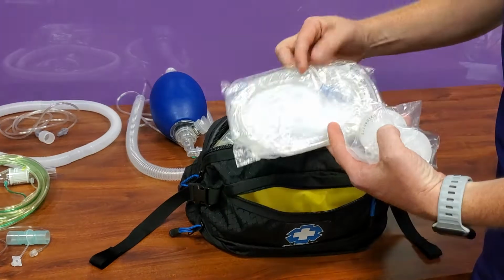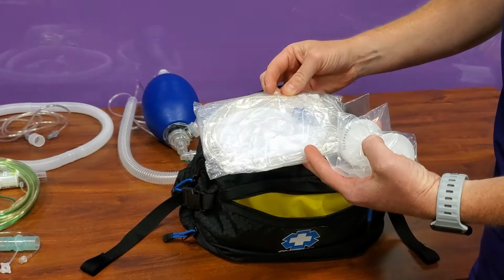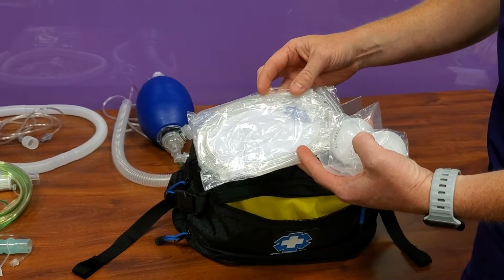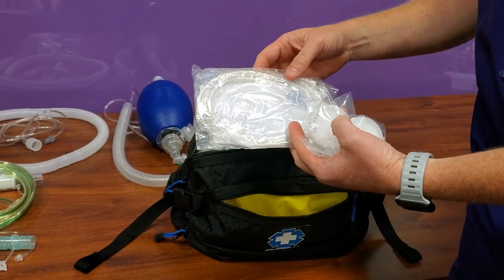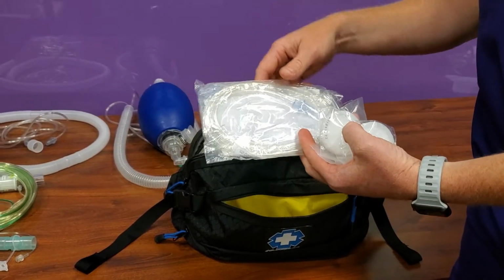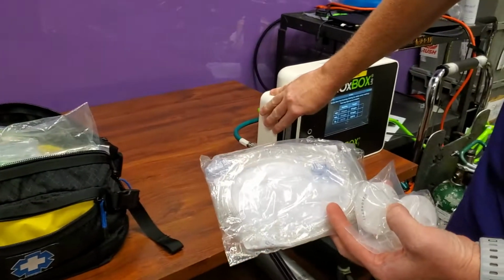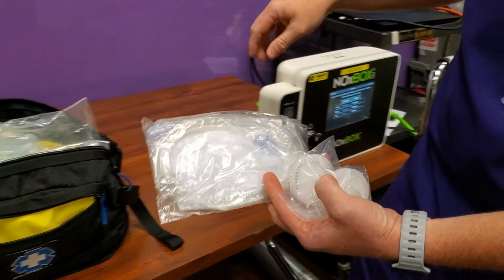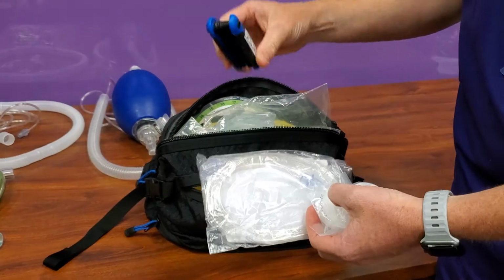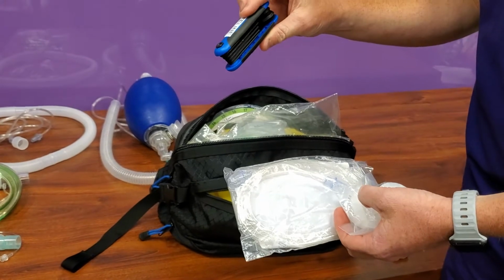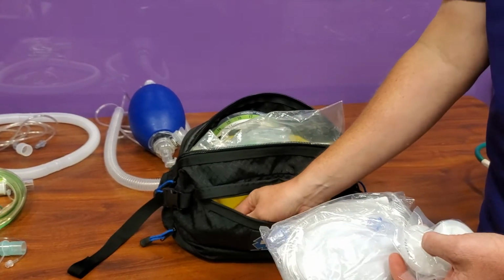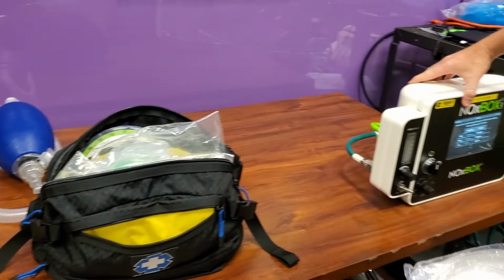We have our backup line here, and this one is used if you did need to bag the patient or the module itself failed and you needed to put the nitric in line for the ventilator, going through our flow meter here as opposed to the set module itself. And last but not least, we have an Allen key set up here. This is just in case there was an emergency. We obviously have had some problems in the past.